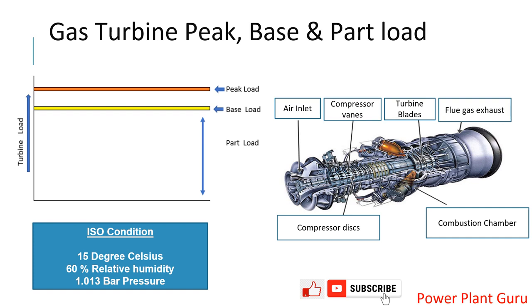Peak load conditions are those conditions where the output of the machine is maximized at the cost of the machine's life. Output is at least 8 to 9 percent more in peak load condition. Since IGV is already fully open at base load, in peak load there is no extra air that can be supplied — only extra fuel is supplied, increasing the heat load on the machine. In peak load, 8 to 9 percent more megawatt than base load is obtained.